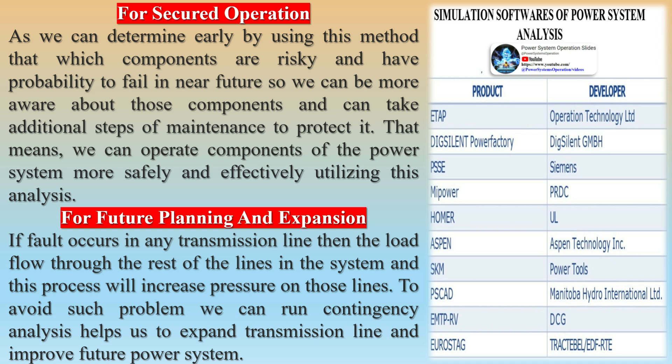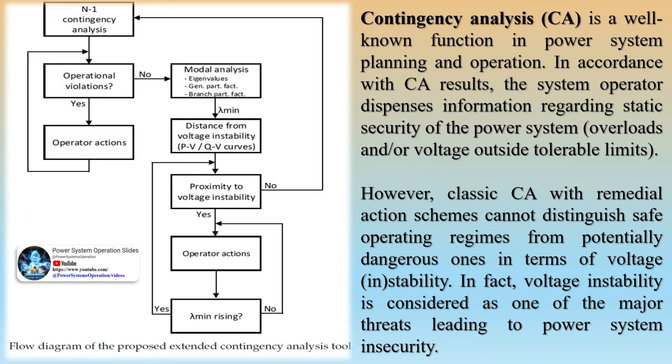Contingency creation consists of every possible scenario that might occur in a power system and involves making contingency lists. Contingency selection is the second stage — the process of determining severe contingencies from anything that might lead to a violation of bus voltages and power. The least severe contingencies are rejected, and the most severe disruptions are considered. The performance index is utilized in this procedure to identify the worst ones.